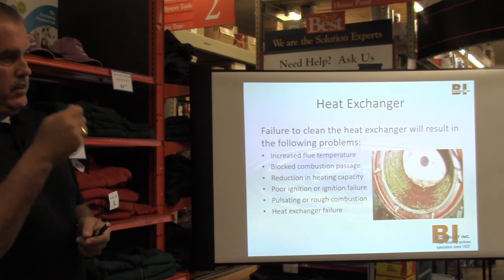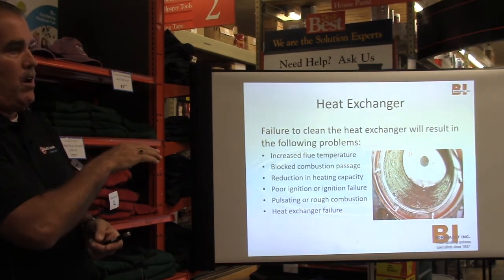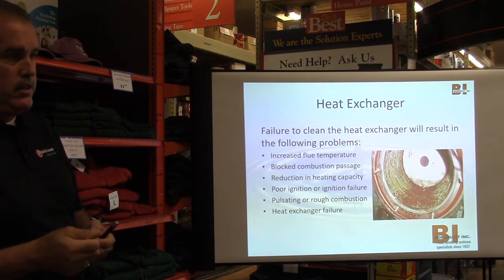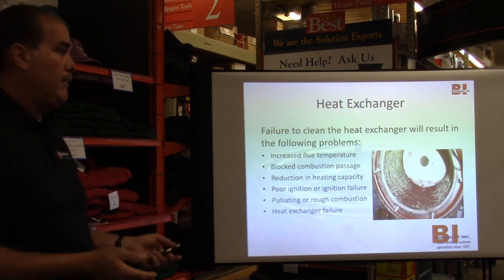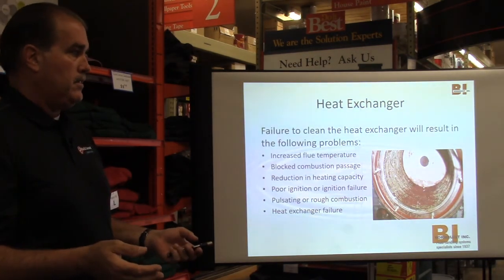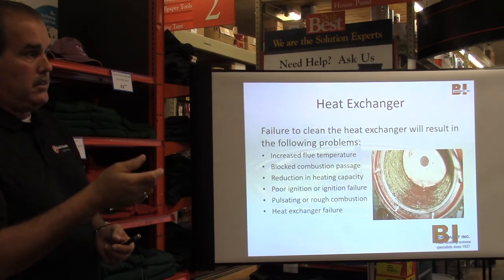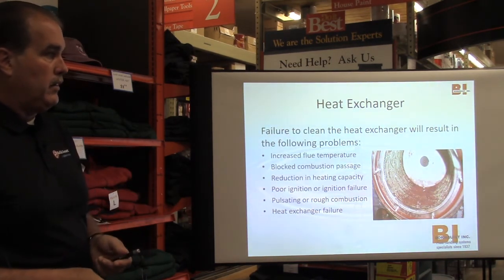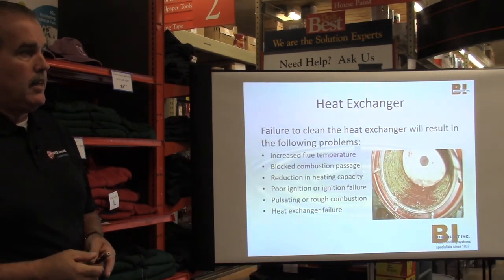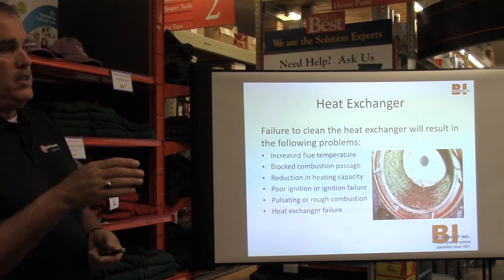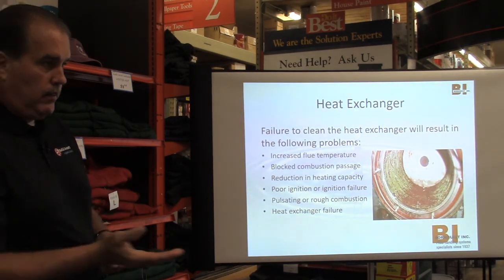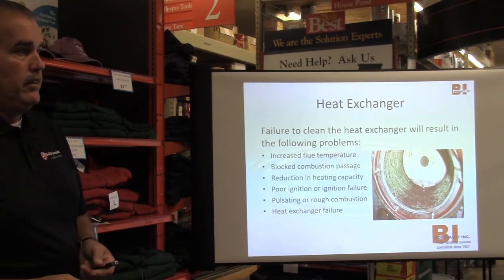Sometimes, rather than water, and I suggest you can use water, a lot of times they'll use nitrogen because they may not have a drain nearby and you don't want to make a big water mess. So that's okay. It's compressed nitrogen they use to blow out the heat exchanger, and that's not uncommon. What you want to make sure they're doing is looking at it. After they blow it out, they look inside to make sure it's cleared.